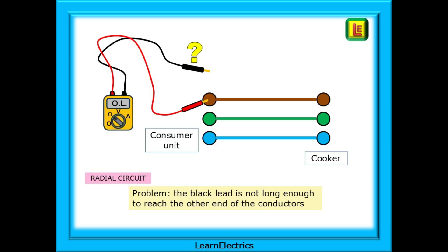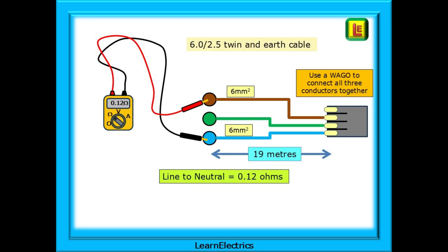The first problem we have is that the test metre probes only have a lead length of around one metre. If we try to measure just one conductor — the line, for example — at the consumer unit, the second probe will not reach the cooker. The same is true with ceiling roses and many other radial circuits. There is an easy solution: use a Wago connector or similar at the cooker end, the point of use, so that we have the other conductors as a return path.